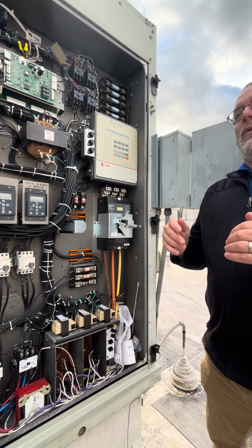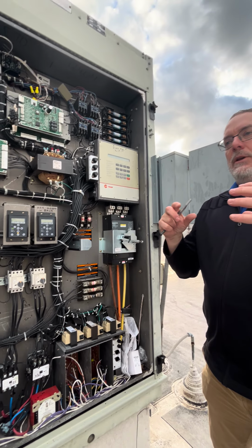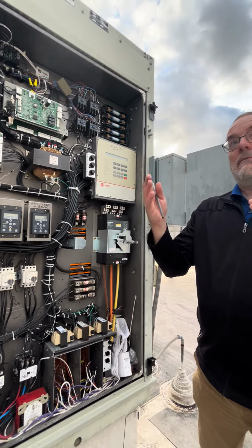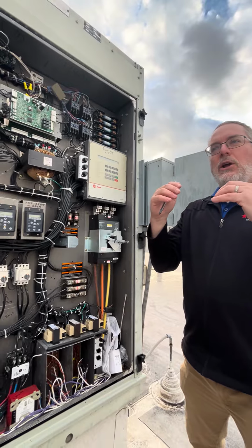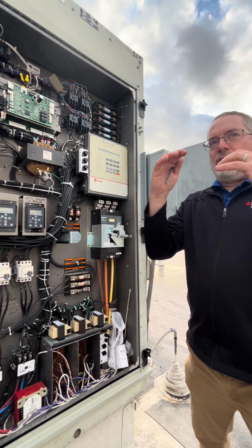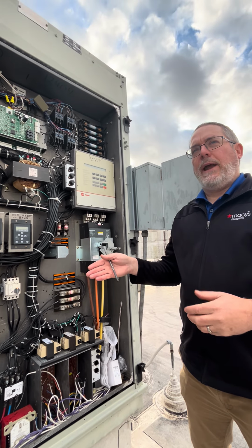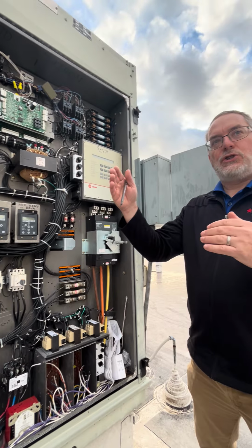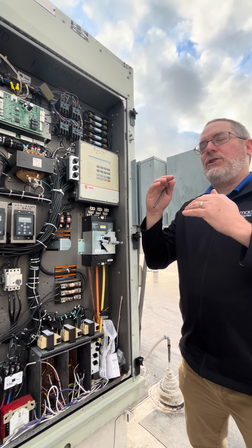Right. So the way it was, a central plant or these rooftops, you'd run a central plant all day, even in a northern climate. Your VFDs might run at 40, 50%. You were giving yourself a 48 degree chill water set point. And it just balanced out because you had that heat load in the building. These units, you ran mechanical cooling all day at a pretty good low discharge temp below dew point. You had constant dehumidification going on. Things were just a little easier.